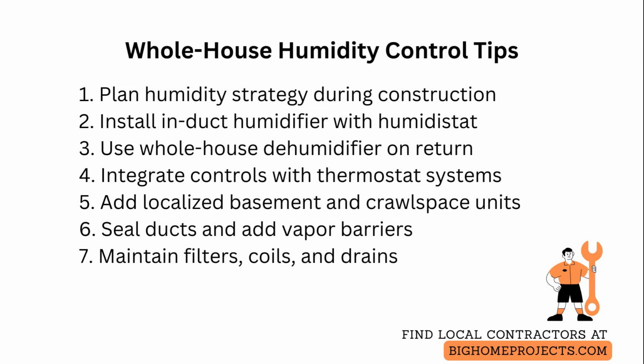For humid climates, place a whole house dehumidifier on the return side of the air handler so it removes moisture before air is conditioned and recirculated. Size it to peak latent loads rather than just cubic footage to avoid undersizing. Integrate humidity controls with the thermostat or building automation so set points change with occupancy and outdoor conditions, and so you can schedule setbacks while away.